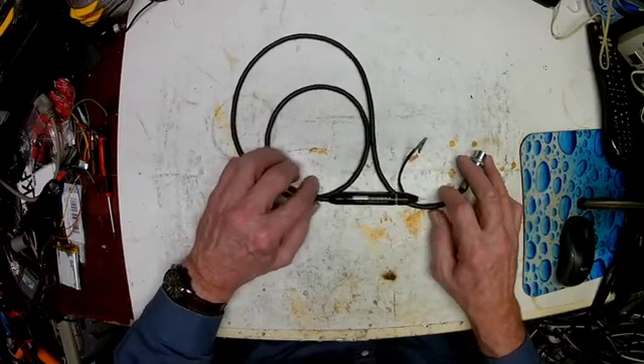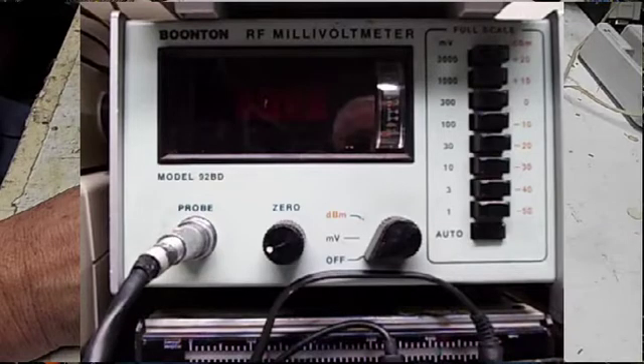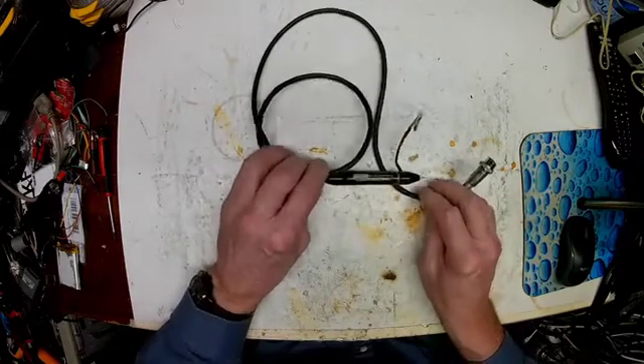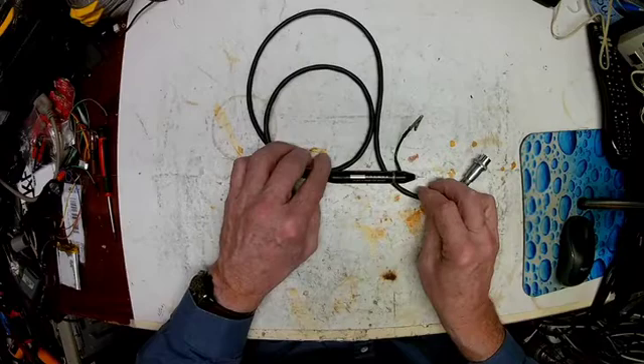Not long ago, I bought this Boonton RF millivolt meter. It's a 92BD, which means that it's digital, and it did not come with this probe. In order to make the meter work, you have to have one of these, and it has to be matched to the meter itself. The serial number on the tag has to match the serial number on the meter, or you're never going to get it perfectly accurate.